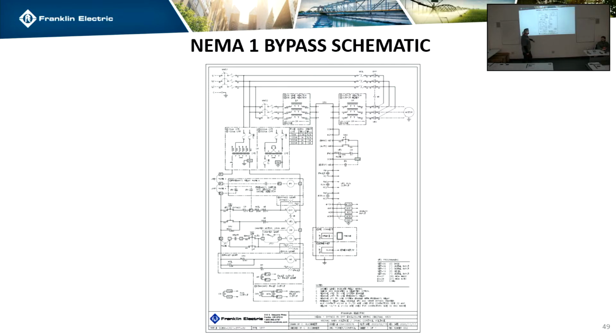And then, the only other thing on here I would notate is this schematic does not have a damper specific option. It just shows you where to wire it. It's going to be right here. It's hard to see on this, but basically terminal 3 to neutral is what you would power the motor with. And then we have a jumper installed, JPD1. If you have an end switch that needs to be made before this thing runs, you just pull this jumper and wire the end switch, and it will lock out your CR relay so that in VFD or bypass, it will not run without the end switch.